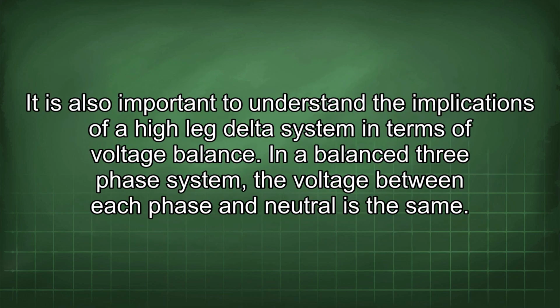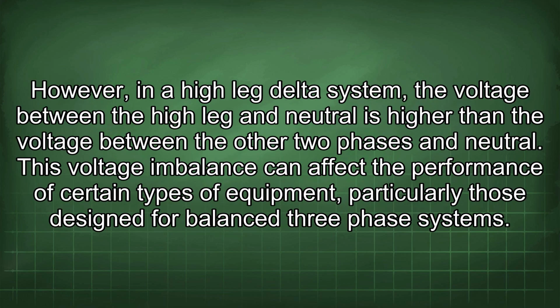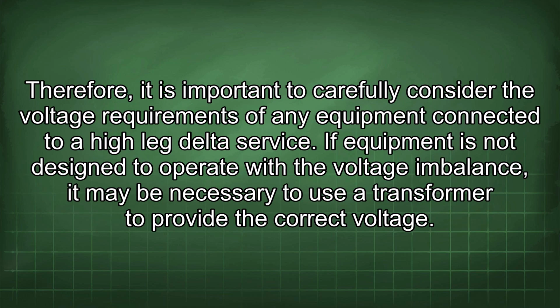It is also important to understand the implications of a high leg delta system in terms of voltage balance. In a balanced three-phase system, the voltage between each phase and neutral is the same. However, in a high leg delta system, the voltage between the high leg and neutral is higher than the voltage between the other two phases and neutral. This voltage imbalance can affect the performance of certain types of equipment, particularly those designed for balanced three-phase systems. Therefore, it is important to carefully consider the voltage requirements of any equipment connected to a high leg delta service.